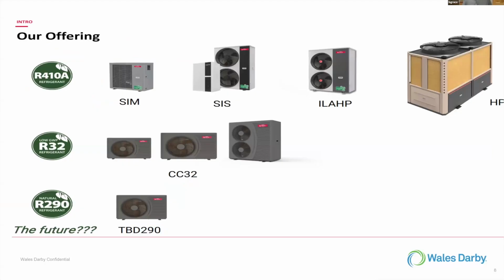So air to water. The offerings coming, we're using lots of different refrigerants right now. Right now we're at the refrigerant R32, which is an A2L version of restricted refrigerant, which has some flammability, but not a lot. We are going to be heading towards some newer refrigerants that are almost as flammable as propane. The advantages to that will be the ability to make the water hotter. Obviously, the biggest issue regarding heat pumping in making hot water for domestic use and for heating is getting the temperature up.